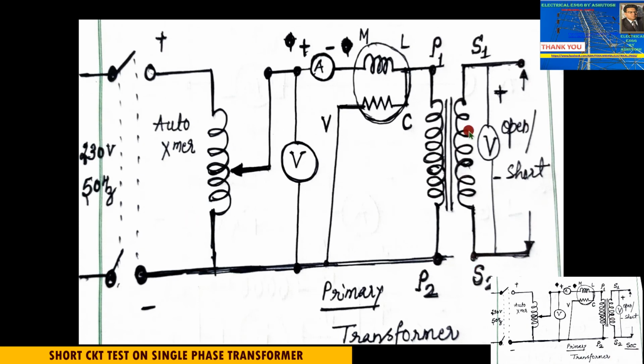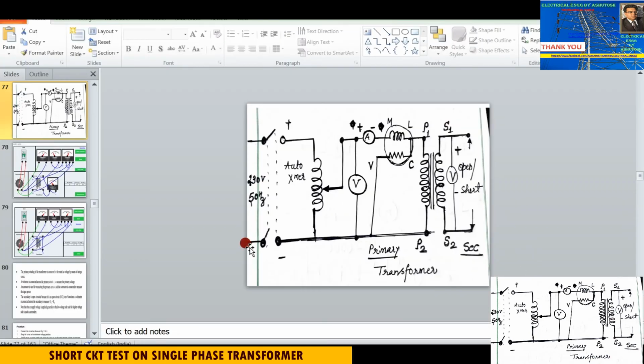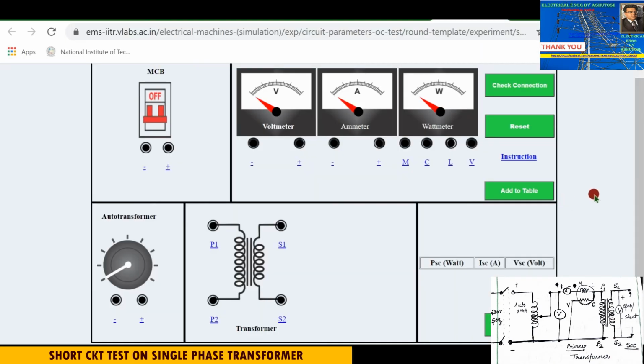The connection diagram is the same, but here the secondary winding gets short circuited. It is kept short circuited, and that is the low voltage winding, and the primary will be the high voltage winding. So all the instruments like voltmeter, ammeter and wattmeter are connected on the primary side, which is the high voltage winding, and the low voltage winding is kept short circuited. The connections are the same, so you can connect.